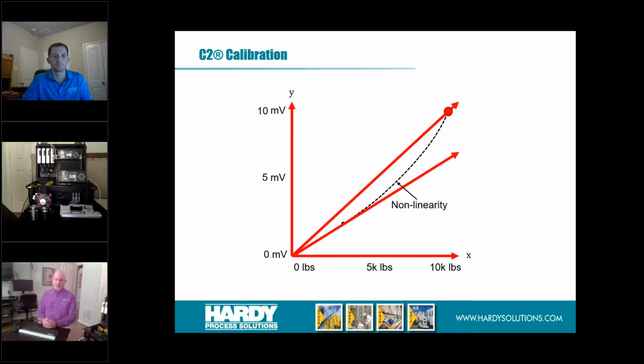So what is recommended on a traditional calibration is that you always bring in something in the 75 to 80 to 90% of the scale's capacity. That way, whenever you do the calibration and extrapolate that out, you have a better representation of what that scale should look like. It's also closer to the ideal scale as well. So that's a traditional calibration. That's what they're doing when they put all that weight on the scale, and then they're calibrating that into the scale.